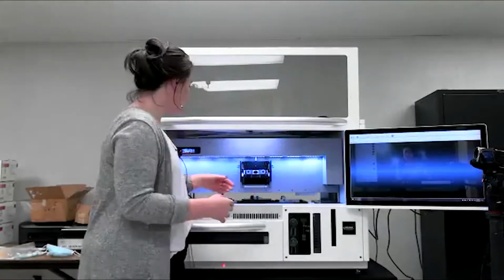It'll bring the platen cover forward, and then you'll be able to wipe off the electrodes just as you would with a lint-free cloth in the Spiffy Touch. You'll do the same thing to the fixed electrodes on the cover, and then place it back on the platen, and there will be a prompt for it to move back to its home position. And you'll just want to do that. Probably, I would recommend it every day, but at the very least once a week. Other than that, we recommend flushing the fluid lines with bleach. I believe we're recommending that once a week. And we have maintenance functions for that in our maintenance menu as well to prompt you through the cleaning process.